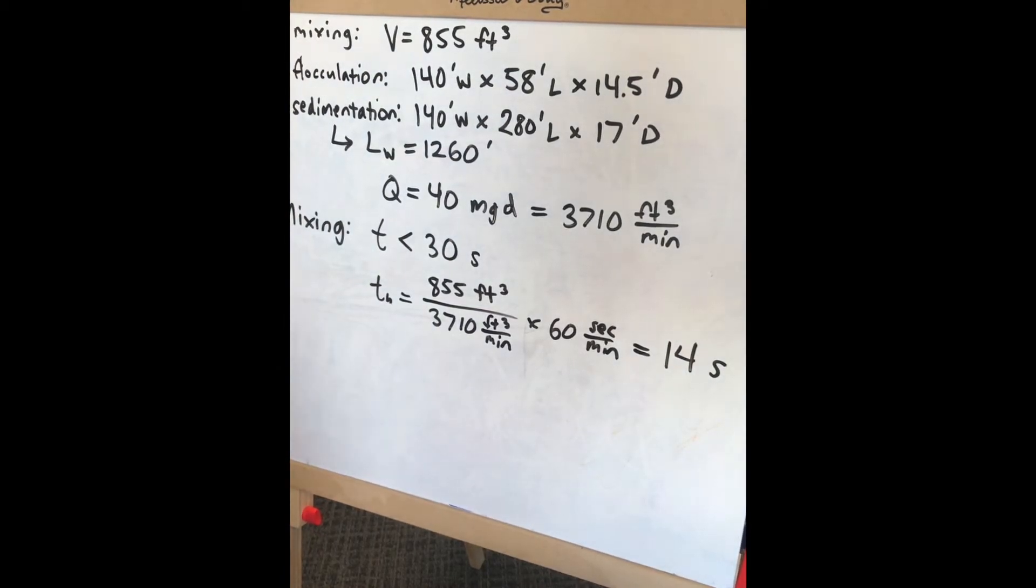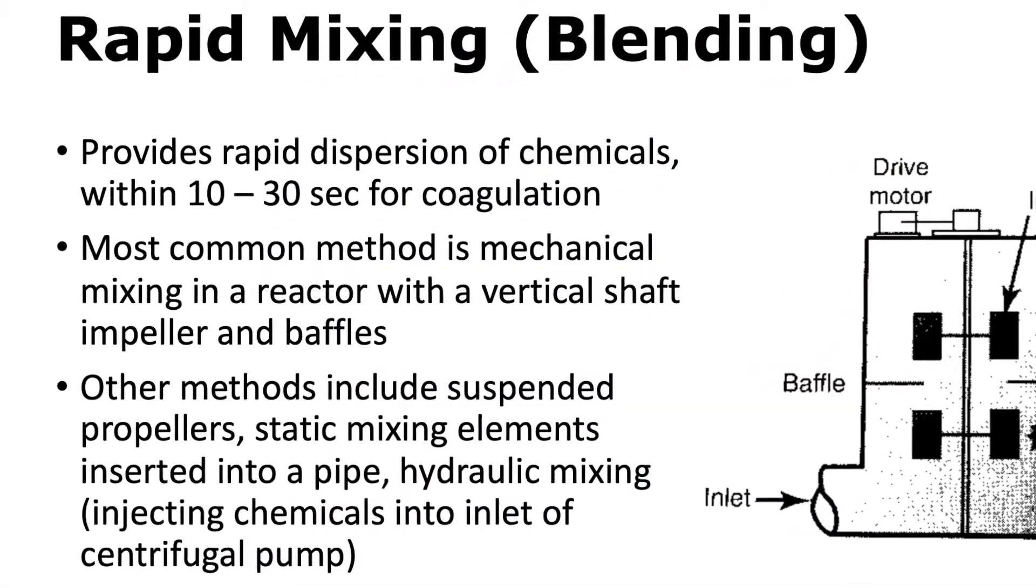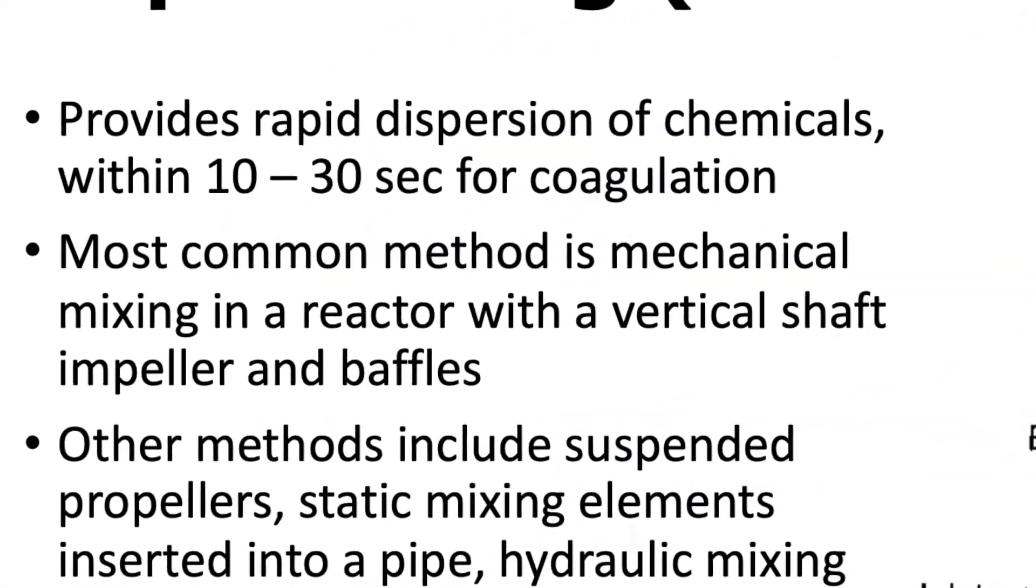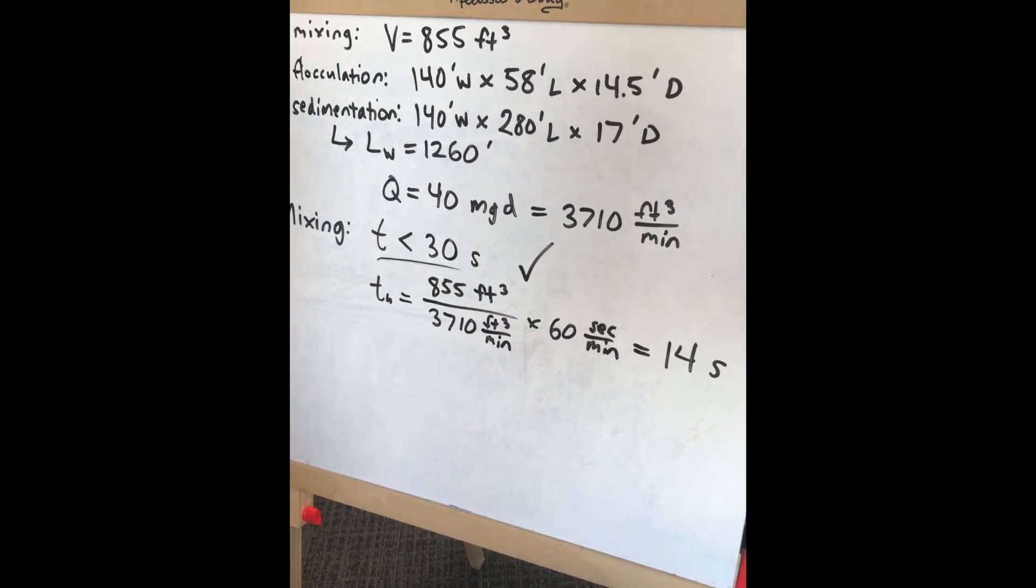This gives us a value of 14 seconds. Since 14 seconds is less than 30 seconds, the rapid mixing chamber meets the design requirement.